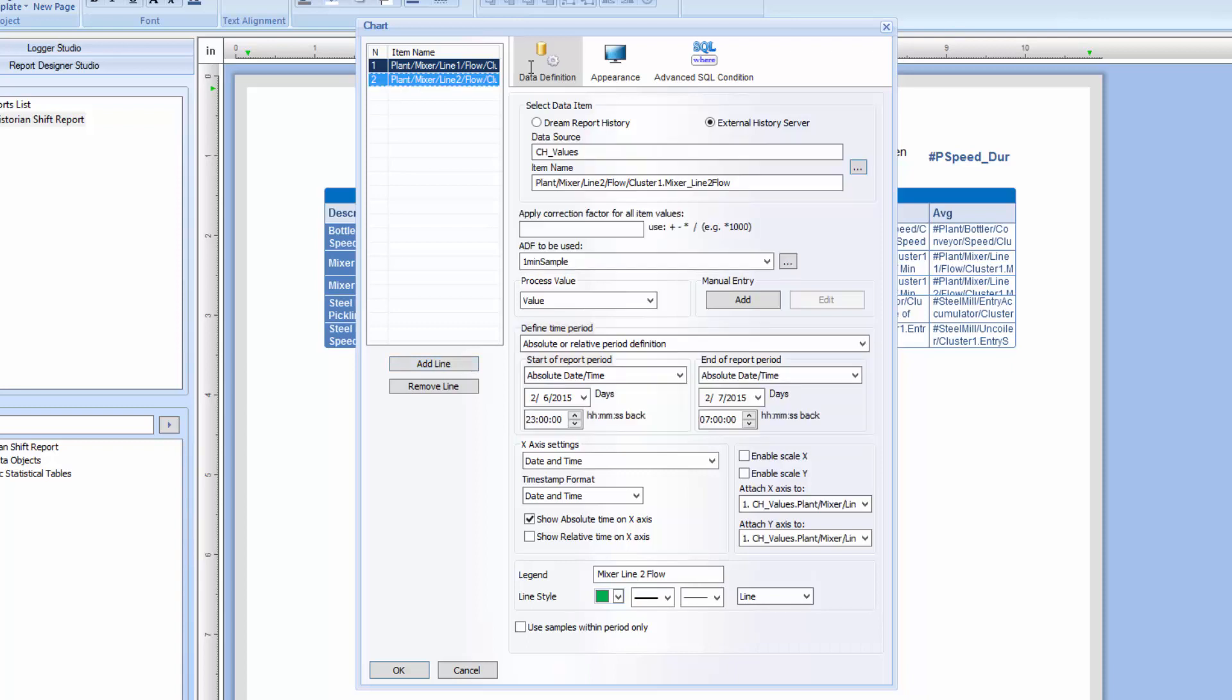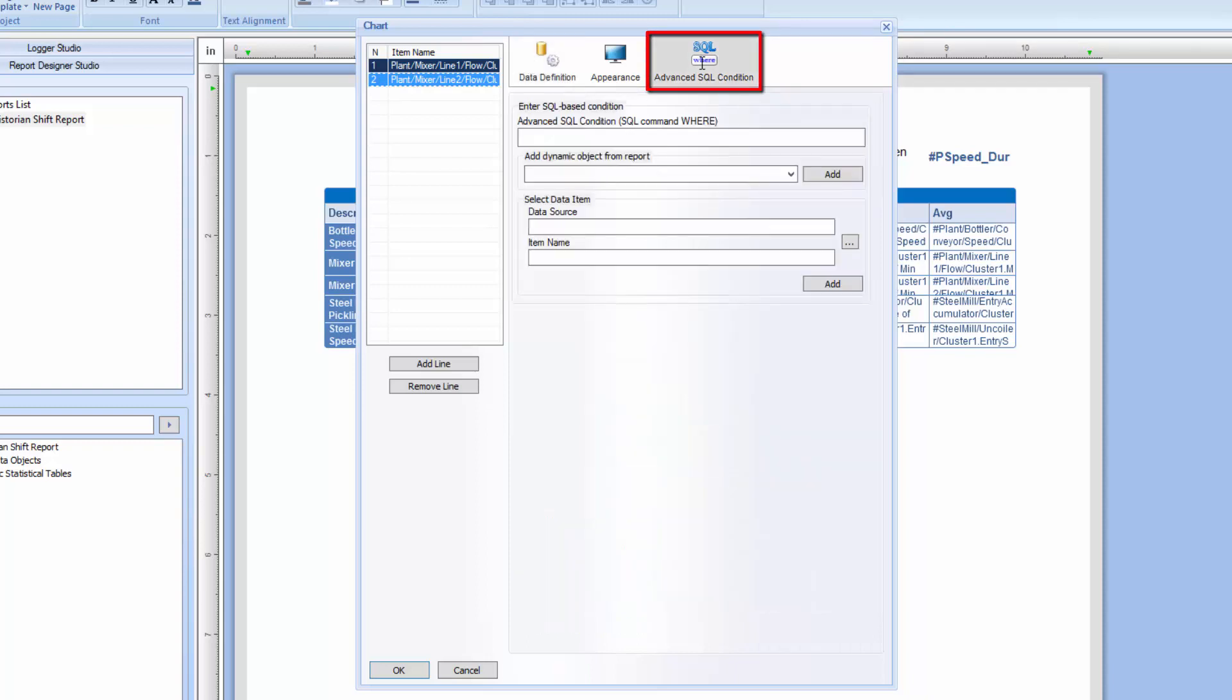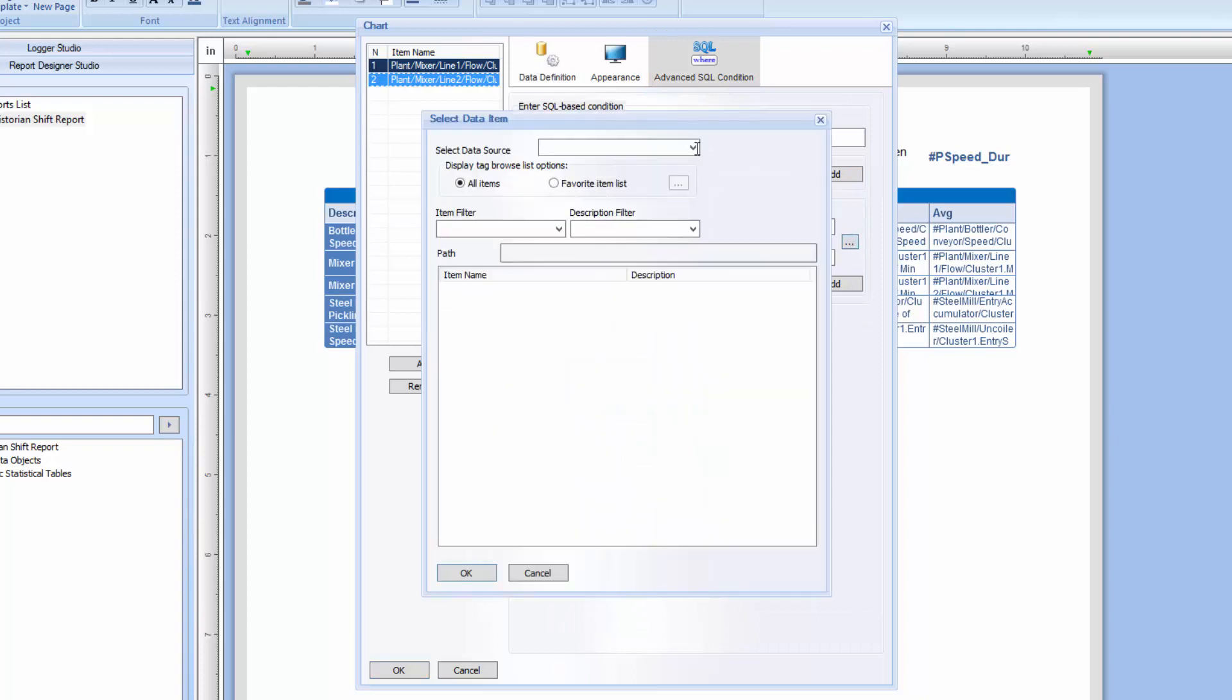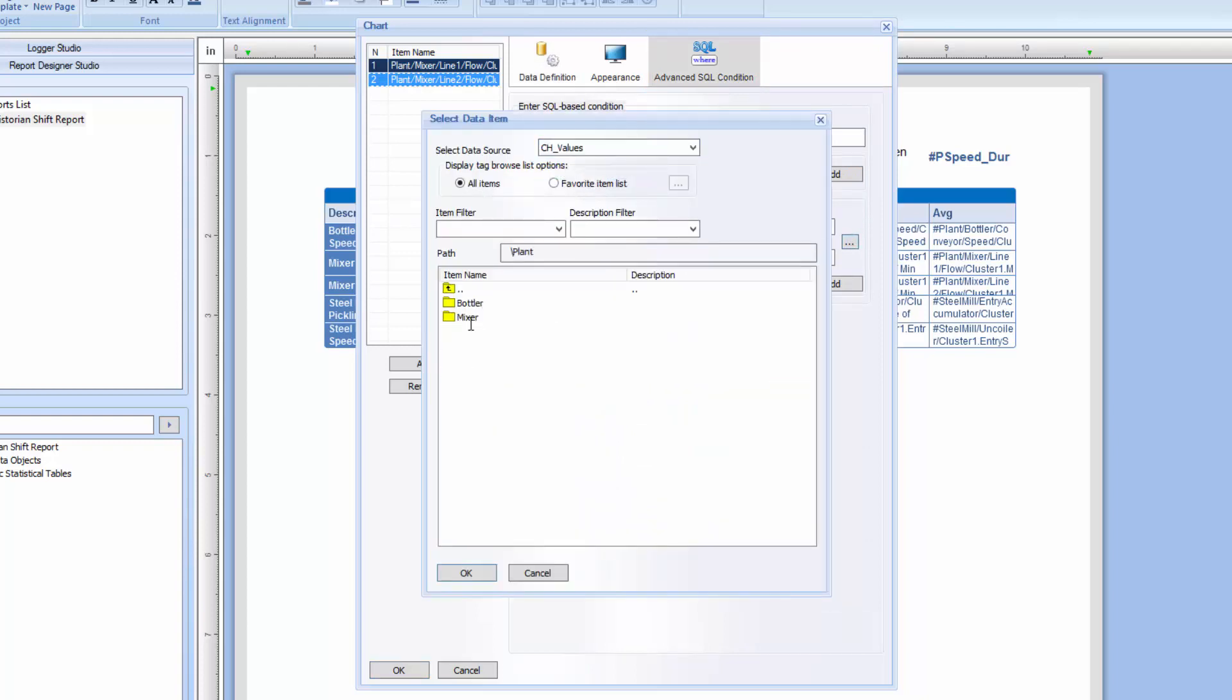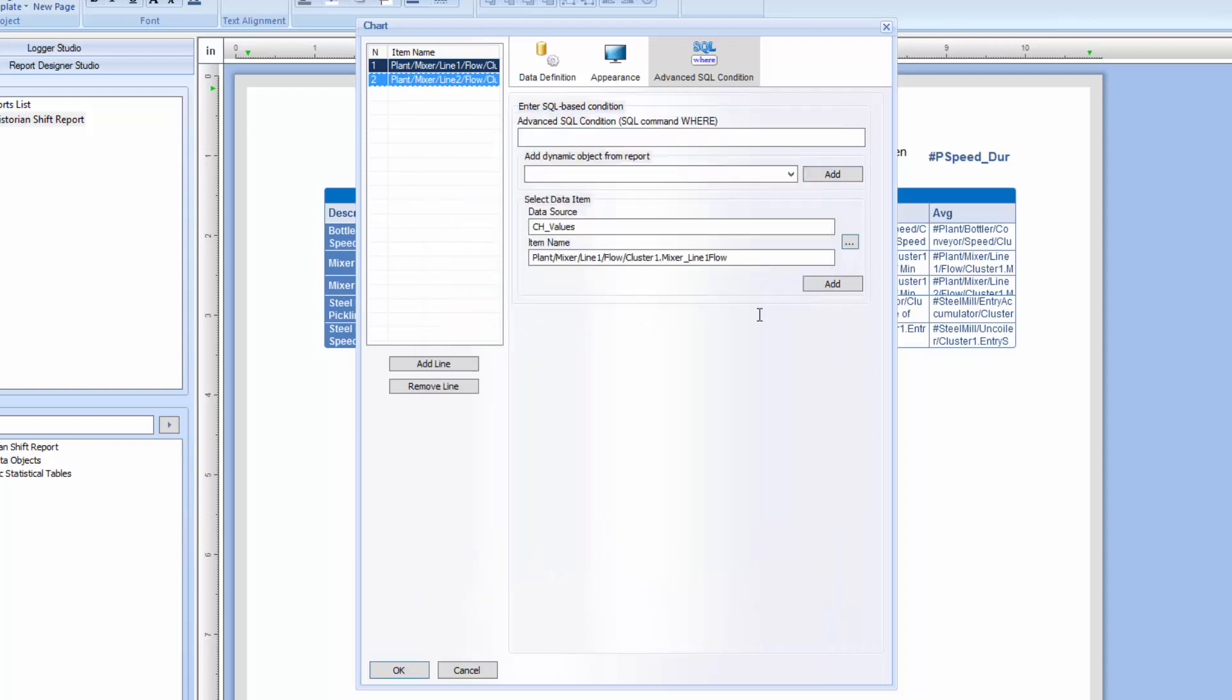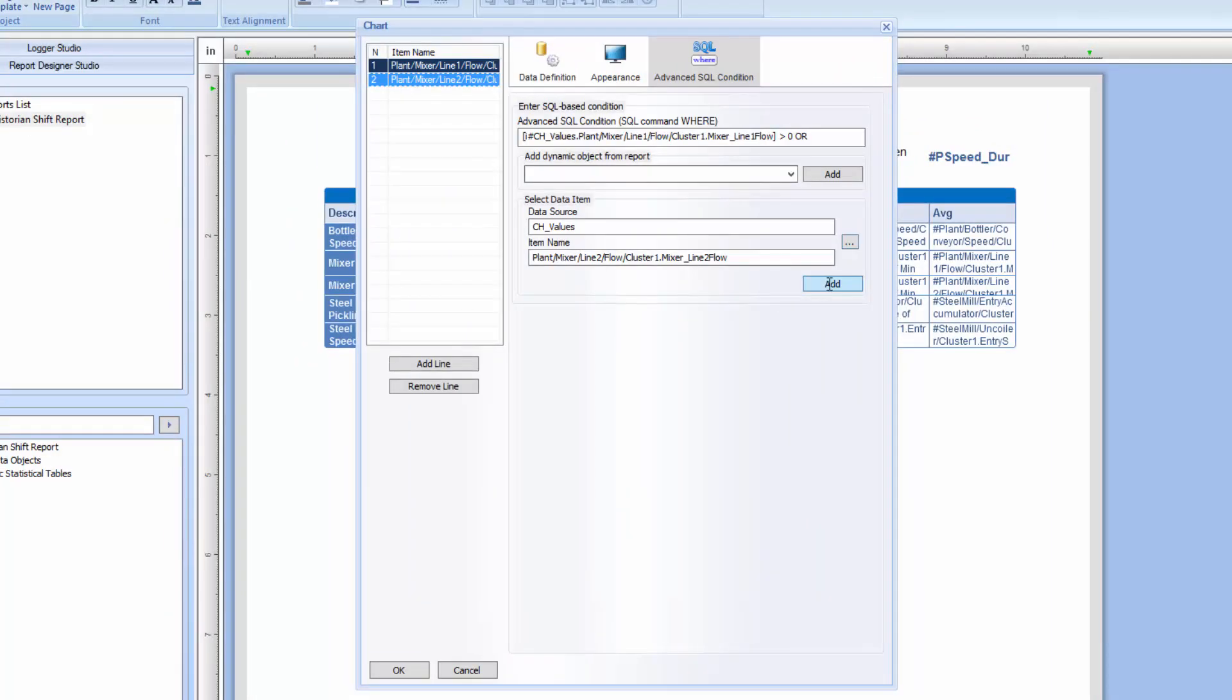I also want to filter the data on this chart to only plot the flows when the values were greater than zero. To do this, I'll apply an advanced SQL condition. In this section, I'll browse for each of these tags and enter the condition where each flow is greater than zero. What we're actually doing here is building a SQL WHERE expression that DreamReport will use to filter the data. Advanced SQL conditions can be applied to data in most objects in DreamReport.